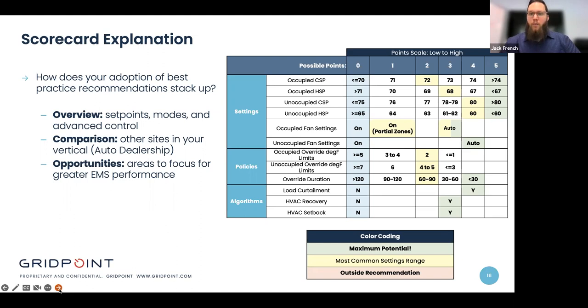On the left-hand side, we have 0 points for units that would be set outside best practice. On the right-hand side of the table, we have our best practice recommendations. Talking about occupied cool set point, we mentioned greater than 74, occupied heat set point, less than 67, then we have our unoccupied recommendations and so on down the line. Of course, setting fans in auto wherever possible is going to prevent unnecessary baseload. If you have a fan in on mode 24/7, you have a baseload for that, potentially even when the site is unoccupied. So that's extra wear and tear on that equipment, and it's also extra energy expenditure for you as the operator.